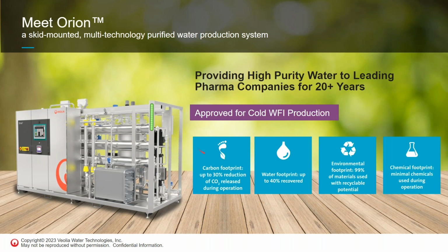And the Mark III, from its predecessors, we can save up to 30% on the CO2 release during its operation with a more efficient way we run the unit. The water footprint, and we'll talk about some water saving innovations within this product in a few slides, we can save up to 40% of recovered water. In terms of the materials of construction, 99% of them are recyclable. And in terms of chemical usage as well, we use minimal chemicals in this system. So it really is a system where we've tightened up on those environmental requirements, but at the same time, we are still compliant.